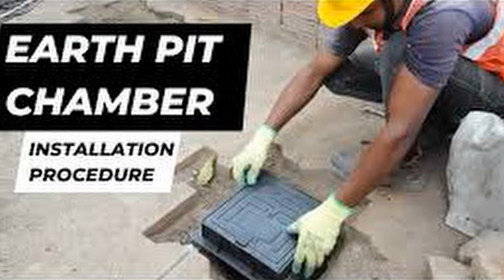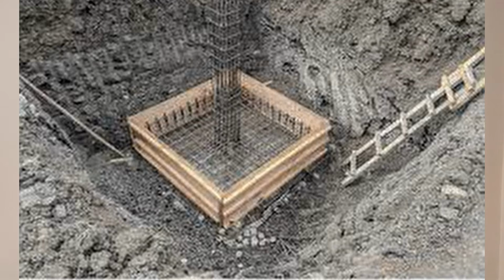If lightning hits, right, that excessive current flows down the conductor into the foundational earth system, and then it would disperse safely into the soil. No sparks inside the building, no damage to wiring, no fire risk. When it disperses, how does it disperse safely into the soil? Because remember, the foundational reinforcement, the rebars, okay, they are themselves in contact with the soil.